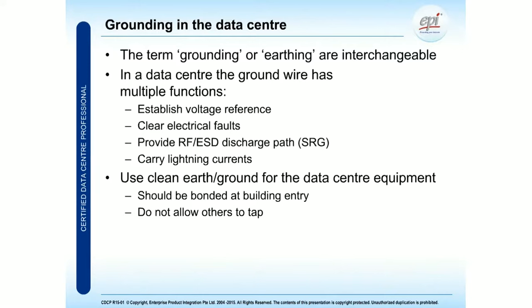Now we talk about grounding, because grounding is very important inside the data center. Grounding and earthing are both the same, and obviously grounding will establish voltage references, but it will also provide a lot of safety. Think about lightning when it hits the building - then the power running through the building should be guided to the ground as well in order to protect your IT equipment, your UPS systems, and so on. So it should be able to carry lightning currents.